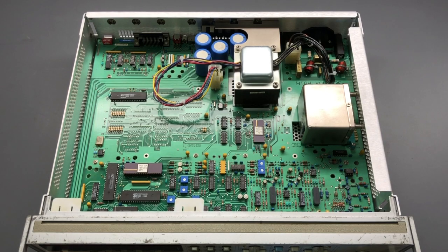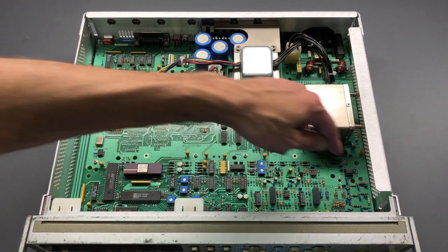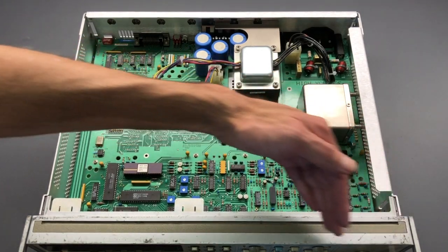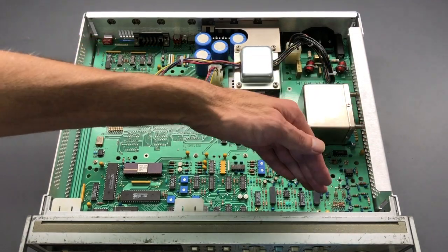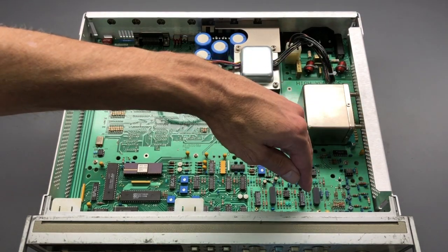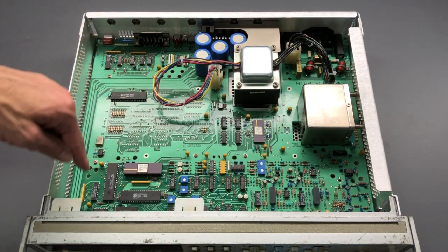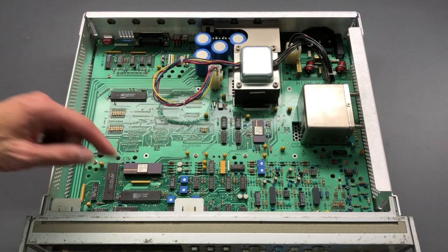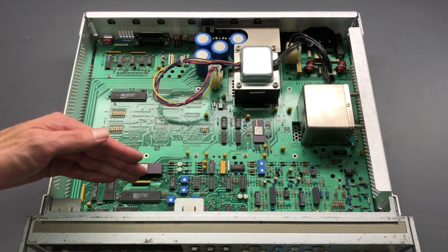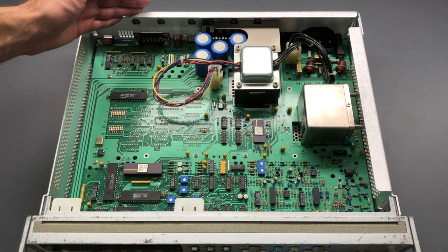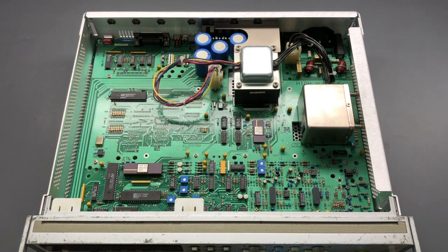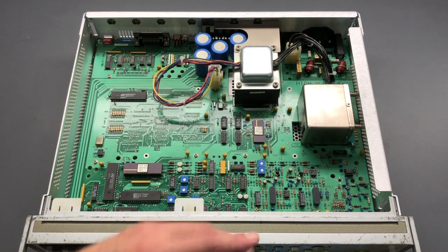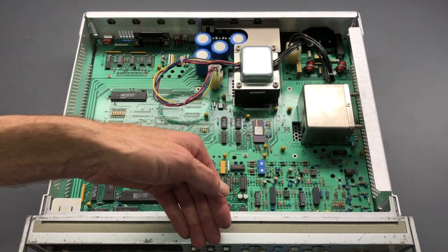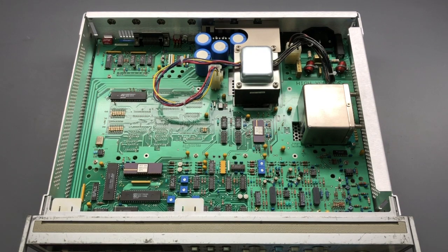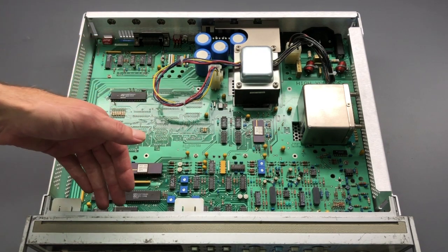So the main signal processing and control is in this front half of the circuit board. Starting over here, we have the input side from the 3 different input channels on the frequency counter. There's some filtering, attenuation, and so on that happens over here. There's analog to digital conversion, and over here is the digital portion of the frequency counter. There's also an interface between the main processor and the external HPIB bus, if that's being used. There's display drivers in the circuitry which drive the LED display, as well as the various indicator lamps that are inside the buttons. Many of the buttons on the front panel have an LED built into them to indicate active functions and so on. So all of that control takes place in these components over here.